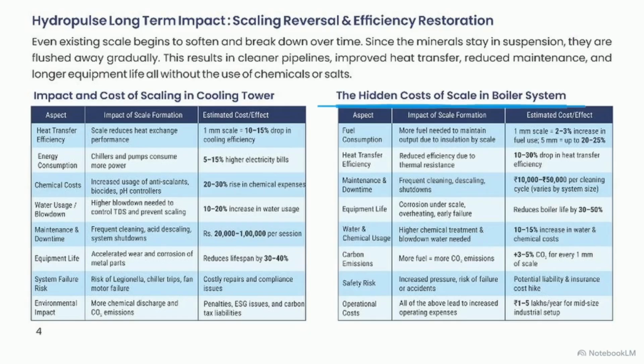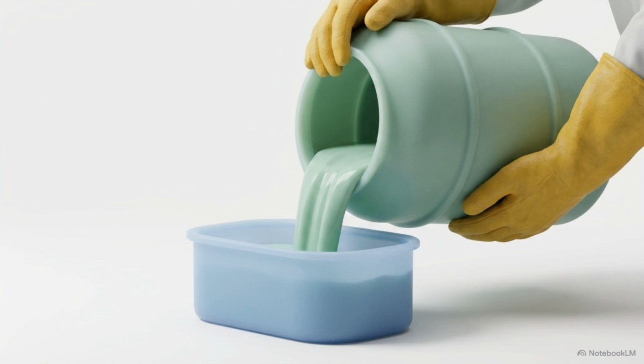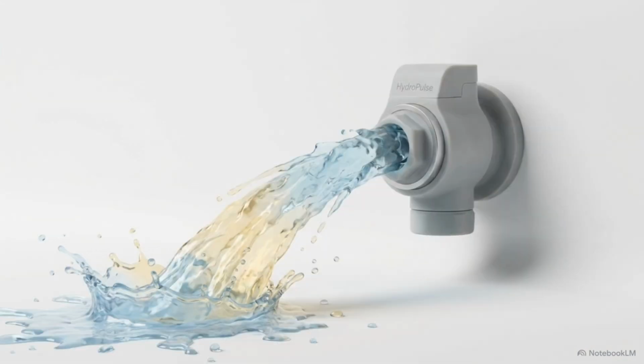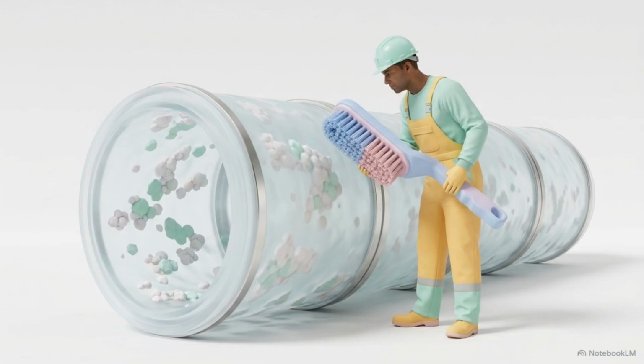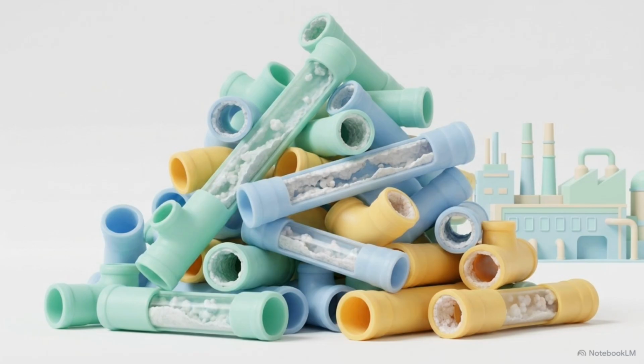This table demonstrates how fast the penalty adds up in a boiler system. A 1 millimeter scale layer causes a 2 to 3% increase in fuel consumption and drops heat transfer efficiency by up to 30%. Fighting this meant dumping harsh chemicals, wasting thousands of gallons through blowdowns, or triggering shutdowns to scrub pipes. Relying on these recurring costs is an unsustainable financial drain on modern global industries.